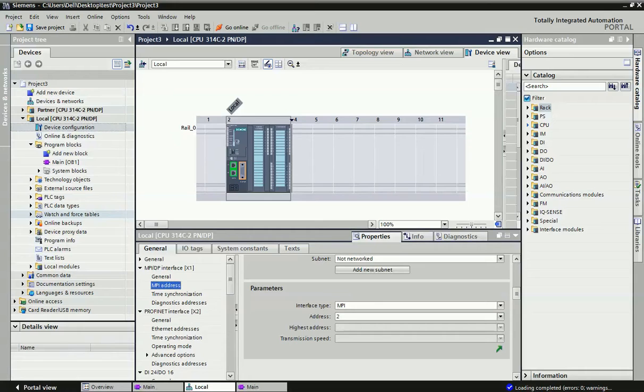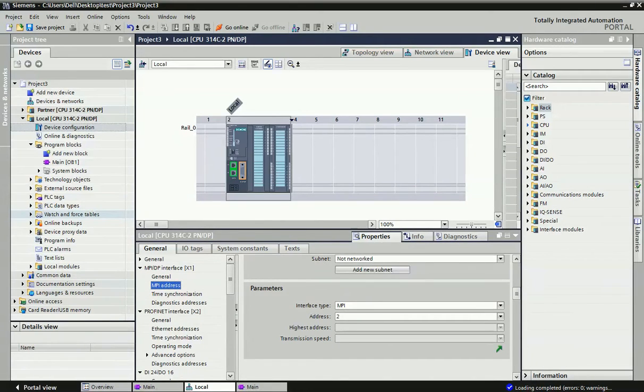Here we will make communication between a local and a partner PLC. In Siemens TIA Portal software, I have configured two PLCs — S7-300 — as local and partner, and we will configure Multi-Point Interface communication between them. I have taken two PLCs, S7-300 314C-2PN/DP, renamed as local and partner.